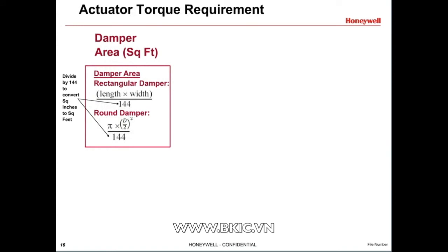You can determine how much actuator torque is needed with some simple math. Start by determining the area of the damper. For a rectangular damper, multiply the length and width in inches together, then divide by 144 to get the square feet of the damper. For a round damper, take the square of the radius, that's half of the diameter, and multiply it by 3.14, and then divide it by 144 to get the square feet.